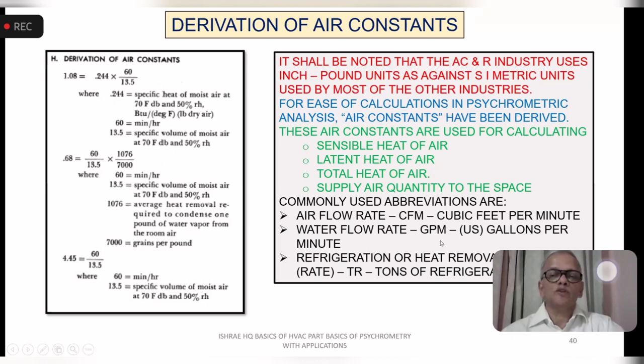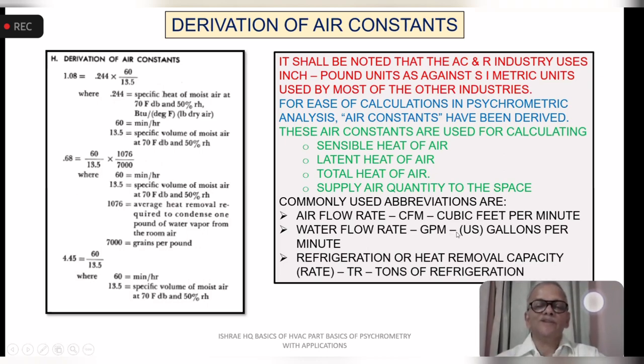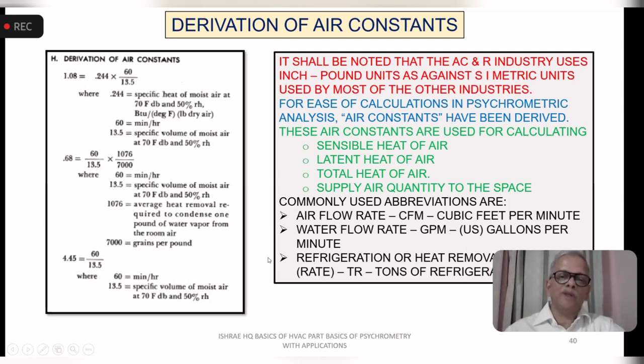US gallons, there is also the imperial gallon, which is higher than this. But in this industry, we are using US GPM. And refrigeration or heat removal capacity, the rate of heat removal, is tons of refrigeration, which is 12,000 BTU per hour, or it could be kilowatts if it is SI metric. All of these units are convertible between IP and SI, but these are the commonly used abbreviations. And how do we get these constants? Now let's look at the derivation of the air constants.